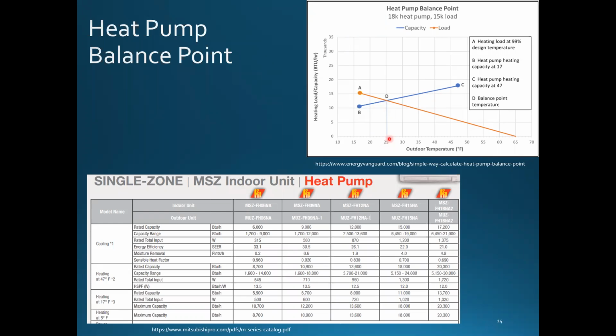So it says, what's my design and what's the output of my heat pump, and where do they meet? And what happens when I need it fast? Do I need auxiliary heat? We've got a lot of places in Colorado, and around the country really, that have air source heat pumps, and it's just an air conditioner. It's able to heat and cool, it can reverse the refrigerant flow, is all it does. But you have backup heat. In Colorado, everybody's got a gas-fired furnace, so when the air source heat pump can't keep up, it flips over to the gas-fired furnace automatically. It's all about controls. But yeah, air source heat pumps are something to look into for you guys.